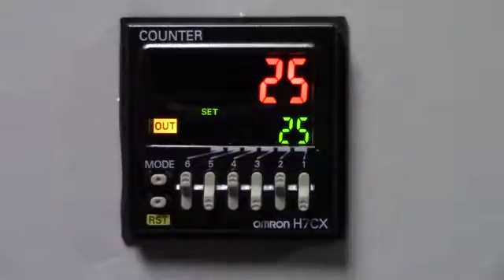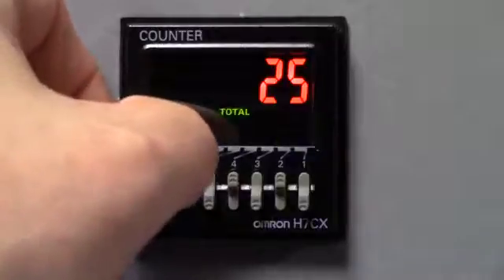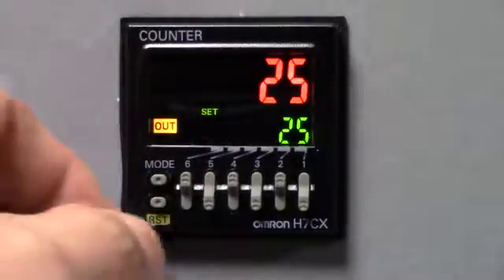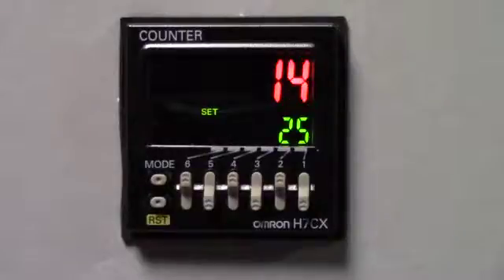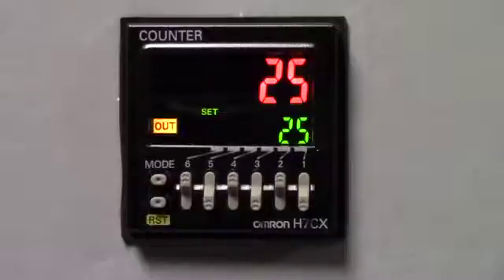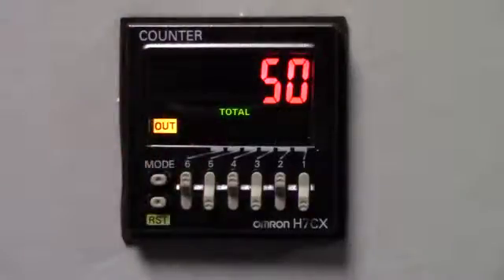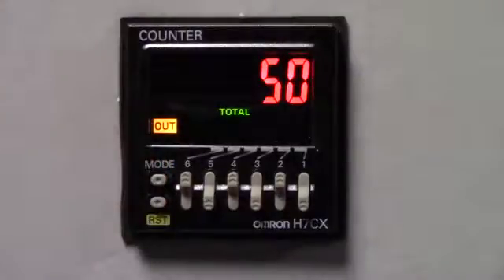And because we're doing a total and preset counter, we now press the mode key. It gives us a total of 25. We press the mode key again, and if we hit the reset key, or press the reset key, and we do another 25. The output light came on, and now we're going to press the mode key. As you can see, it is still keeping track of how many counts we have from a total perspective.